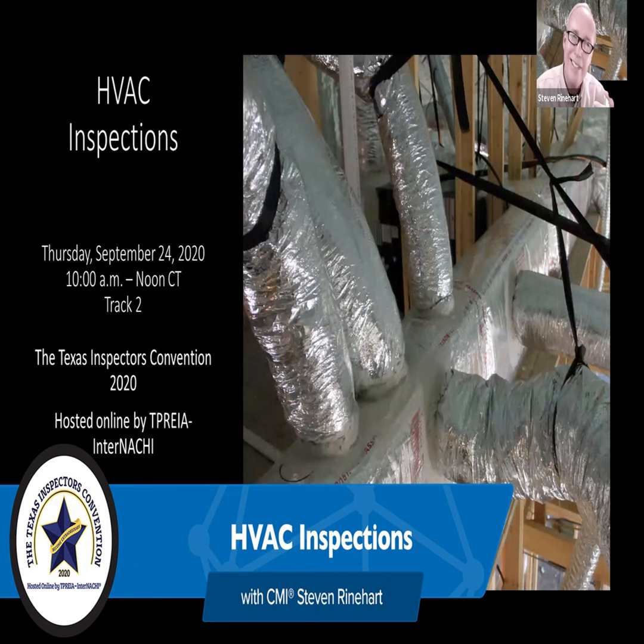There's no restriction on electric strip heat, other than you get some looks from the occupants when it's 98 degrees and you're like, I've got to check your electric furnace. You'll get some looks. I just want to see that it cranks up, heats, and puts out some heat at the register. I'm not going to run it a long time. I put it in the report that I didn't run it a long time, but I wanted to make sure it just heated. Distribution system, I can evaluate with air conditioning.